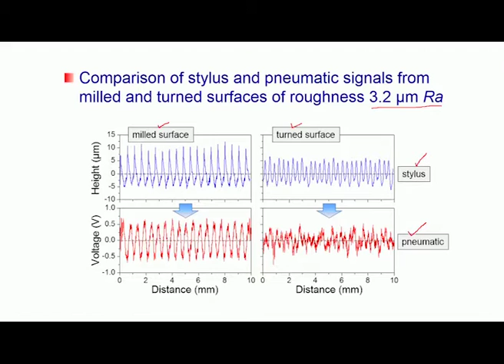Now, these pictures show the comparison of stylus and pneumatic signals from milled and turned surfaces. You can see here a milled surface and then a turned surface of roughness 3.2 micrometer Ra. Standard surfaces are used for calibration purposes. These are the results obtained by using the stylus instrument, and these are the results obtained by the pneumatic surface instrument. The output is in terms of voltage, and this can be converted into a roughness value.